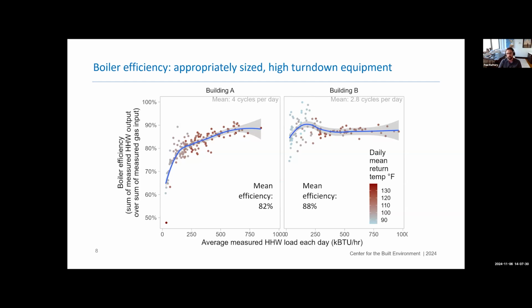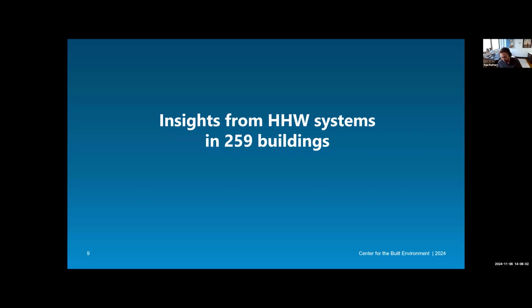So even in this case, where we're really aggressively sizing, they're still performing below nominal efficiency. The building on the right there should be at about 95% average efficiency if you weight it by the low return temperatures here. But you can still see if you were to replace that 50% efficient boiler with a plant like this, you could almost halve the natural gas emissions in this building by really aggressively capturing that energy waste, right? So there's lots more information on that in the paper on that topic.